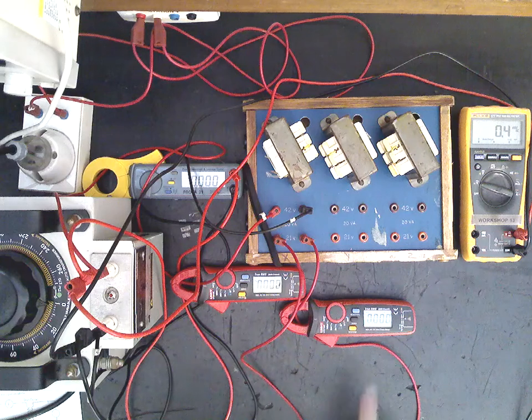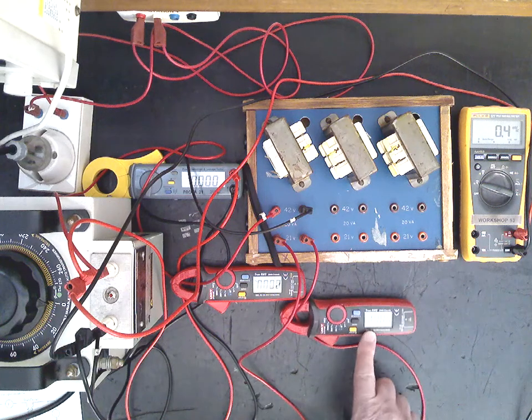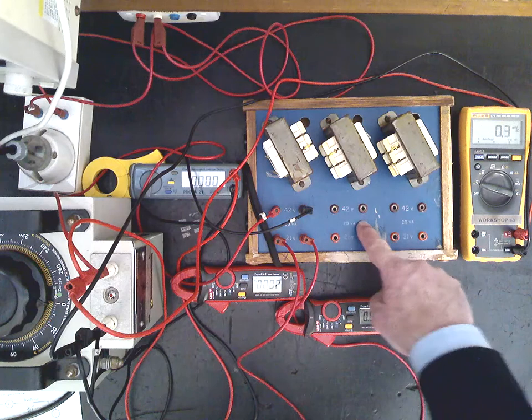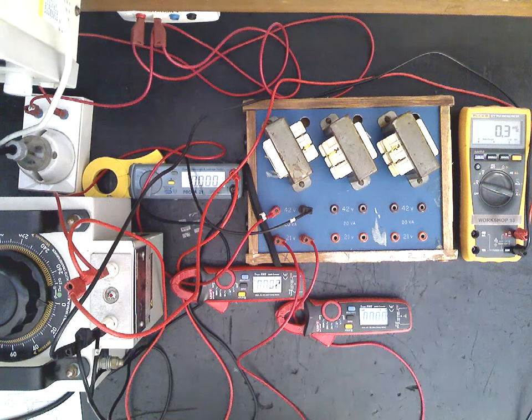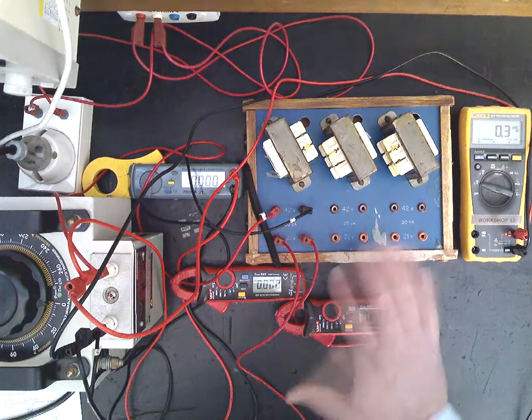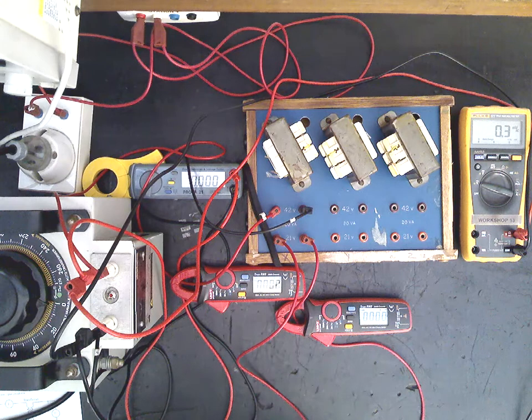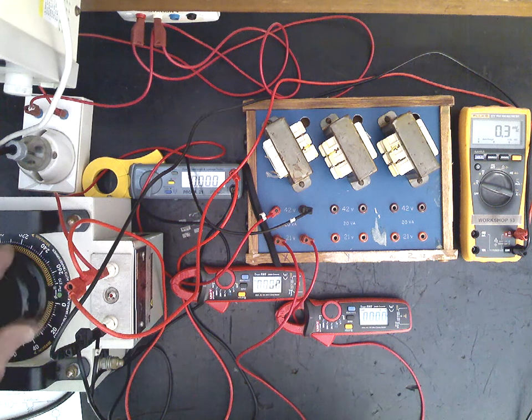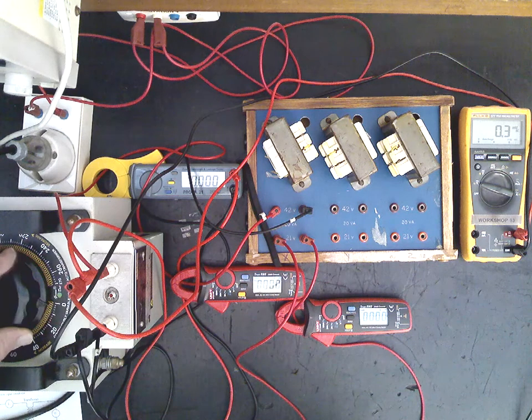And so we want to bring this up to full load current for the transformer, which is, as we said, it's 20 volt ampere is the output power rating of the transformer at 21 volts. There's around about that one ampere full load current.